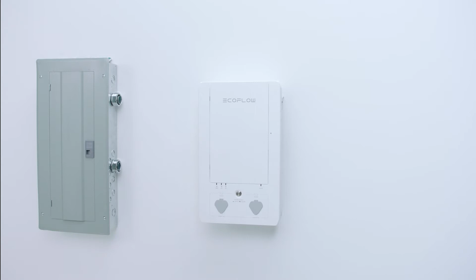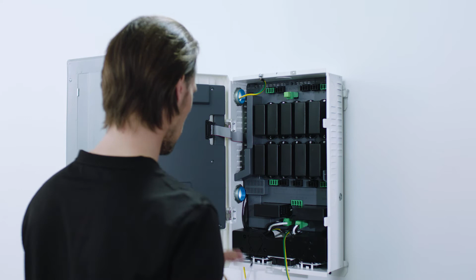Remove the desired knockouts on the Smart Home Panel and the main breaker panel and attach the conduit and conduit whip. Connect the ground wire to the ground bus. Connect the output wires. They are labeled 1 out to 10 out. Connect the input wires. They are labeled 1 in to 10 in.